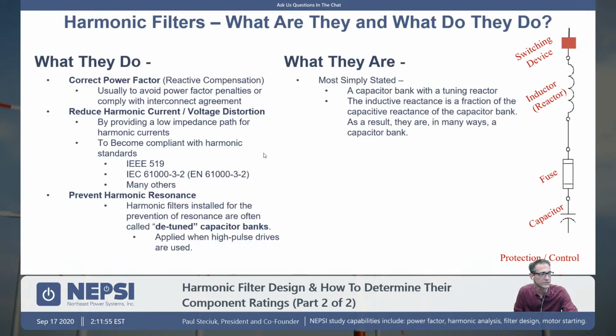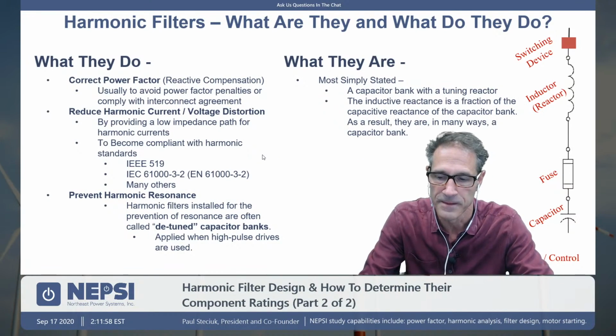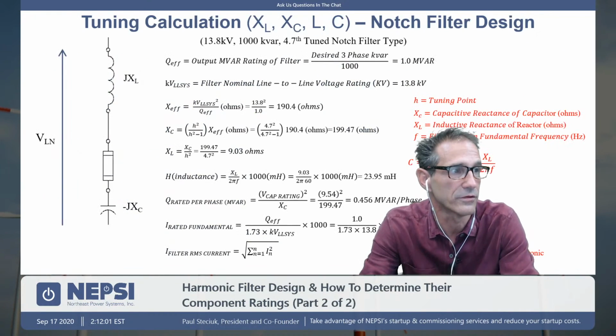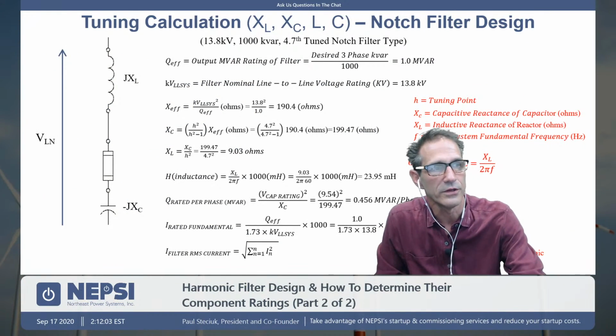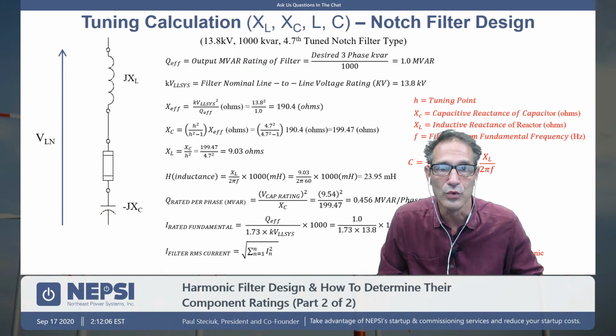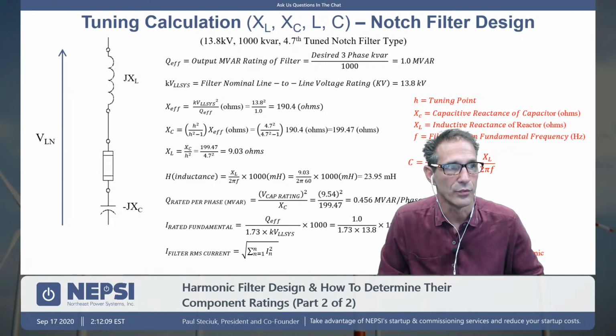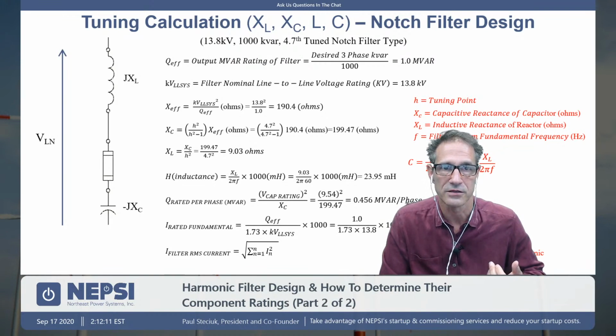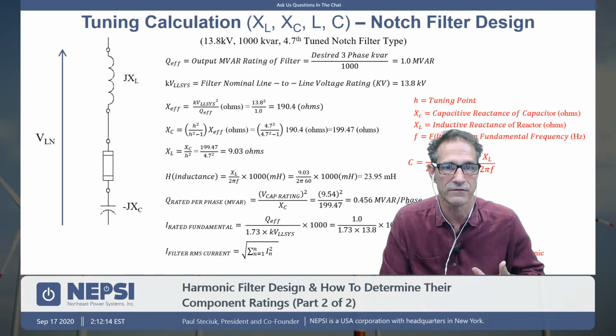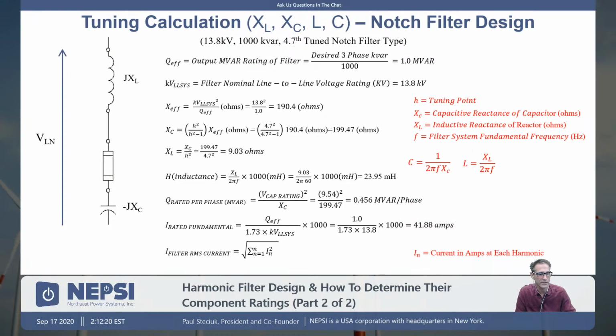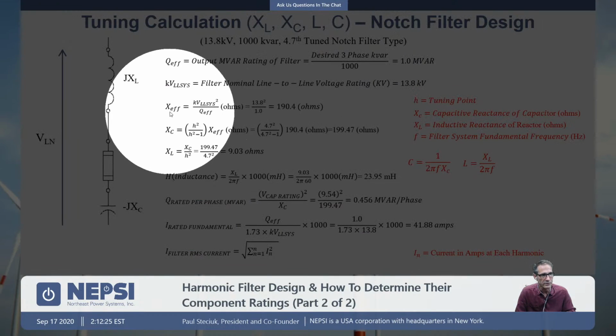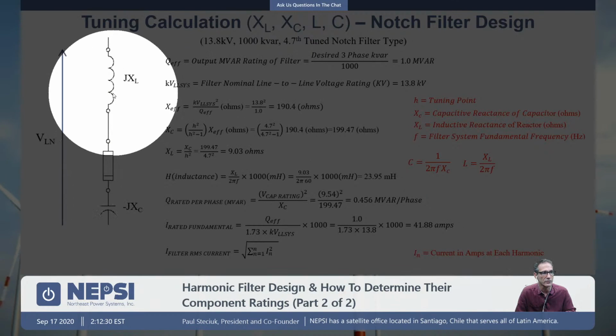So I'm not going to go too much into what we talked about last week. I think that you would be better off to go through it in detail. But last week we got to the point where we were talking about the tuning calculations, and we reviewed three types of filters: the notch harmonic filter, the high-pass harmonic filter, and the C high-pass harmonic filter. The tuning point calculation is about the same. It's the same exact concept. We are always looking to calculate X effective, which is basically the total impedance across the harmonic filter based upon a value of Q effective, which is the output kVAR.